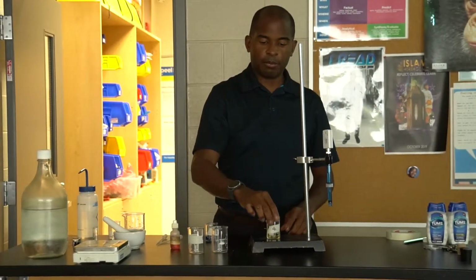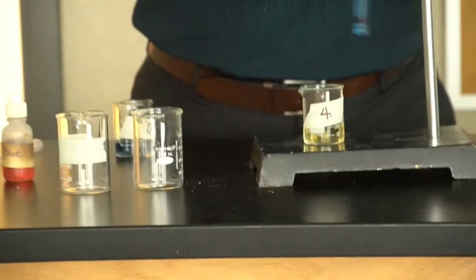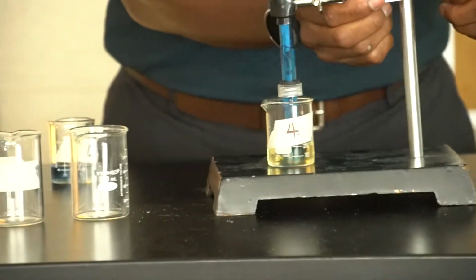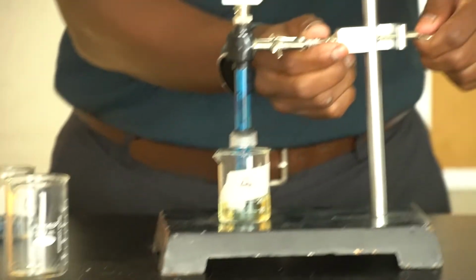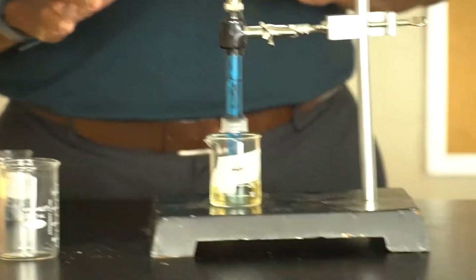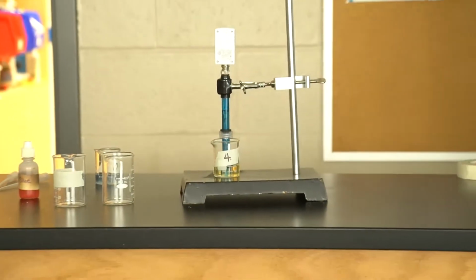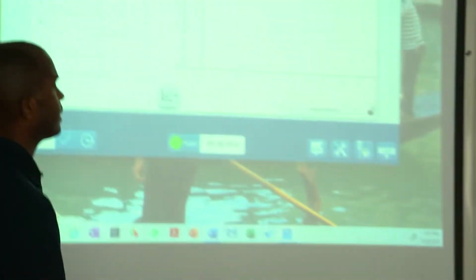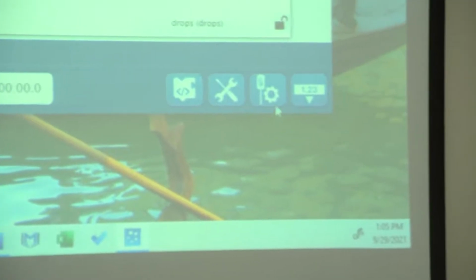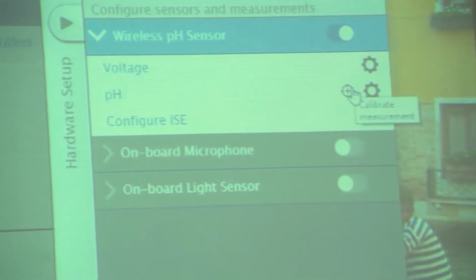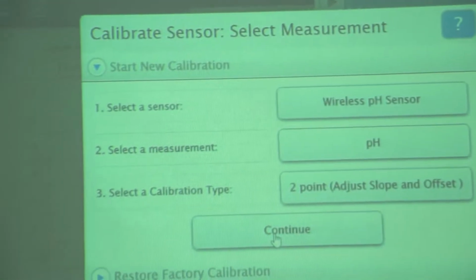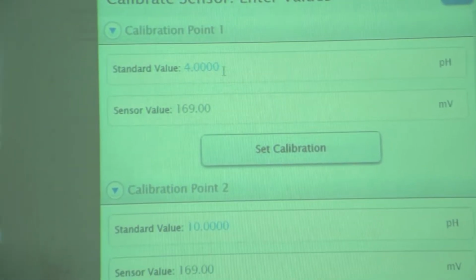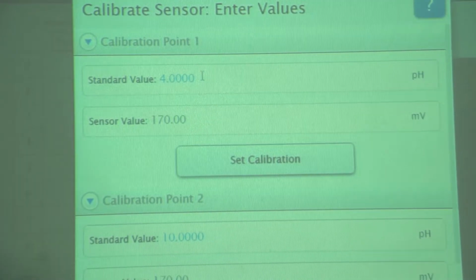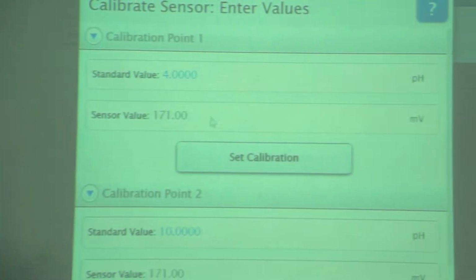So my pH 4, I'm going to place on my reaction space. I'm going to take my pH sensor, I'm going to drop it into the liquid. Generally speaking, I don't want my probe to be moved when I'm calibrating. Now that I'm setting the pH buffer 4, I'm going to go back to the computer, the application. I'm going to select the screwdriver tool, and beside the pH is a little target. I click on this, and it's going to give me the calibration screen. I click on continue. The value I'm currently using is a standard value of 4. It's been sitting there for over 10 seconds, so it's good to go. I click on set calibration.